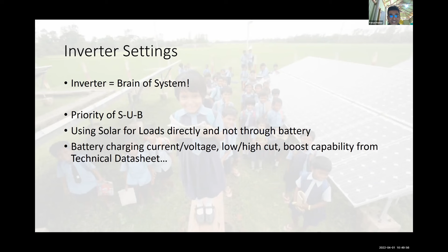There are also other things like battery charging current, voltage, high cut, boost capability - we take these values from the technical data sheet. However, there's been an issue - this is an example of the data sheet that was provided, and unfortunately there is no technical information here at all. There's just one line that says for 10 hours it has 100 ampere hour, so if we divide 100 by 10, it's like 10 amps, but that's pretty much it. So again, continuing what I said earlier, if we get the proper technical information, the battery longevity will increase.